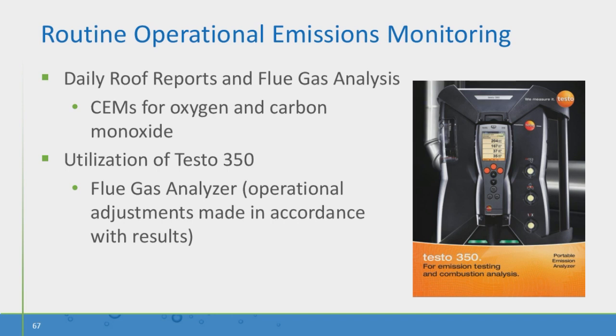If our NOx readings indicate a high value, we may need to back off on our gas as long as we can with our temperature limit, or back off on our sludge flow and adjust our oxygen.